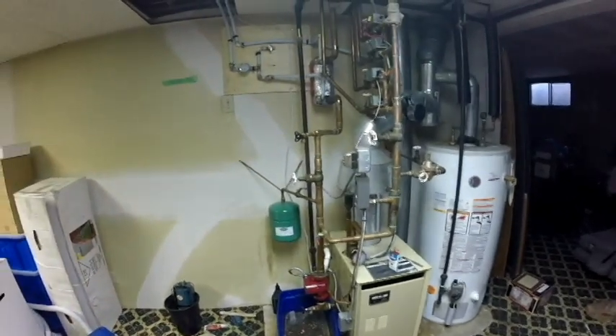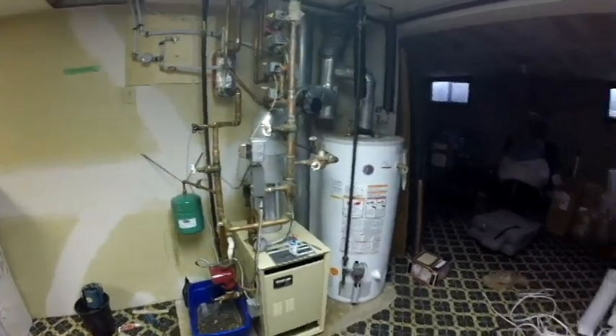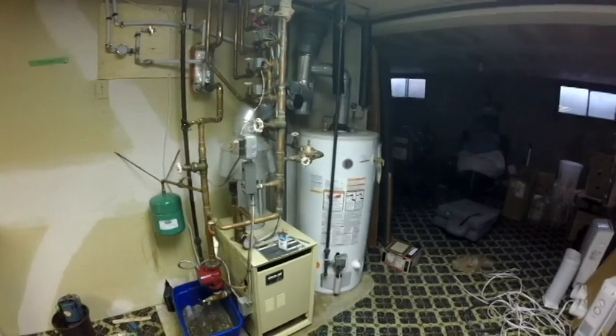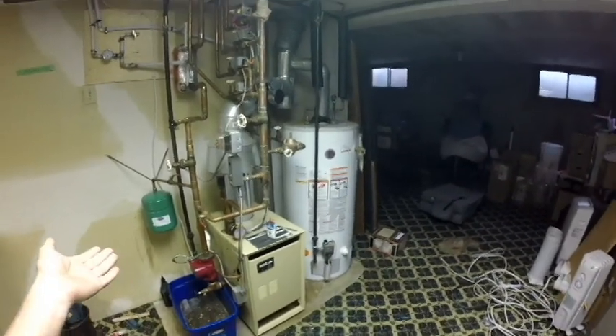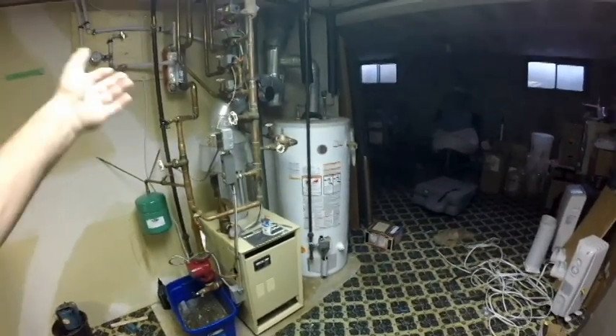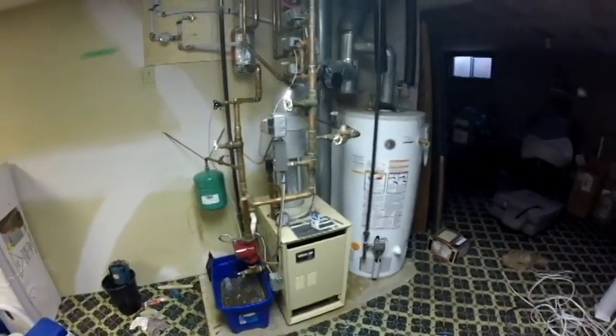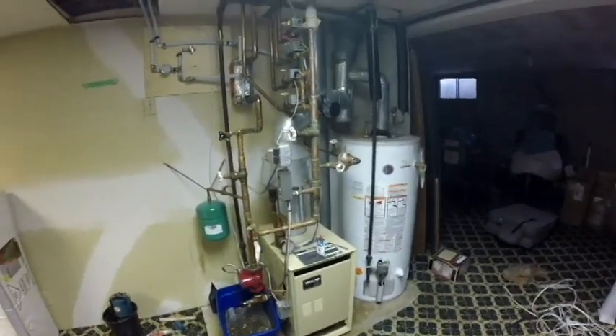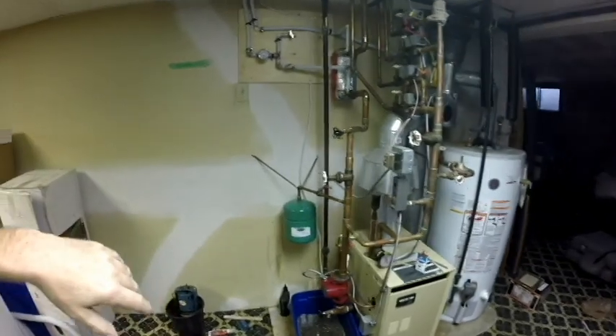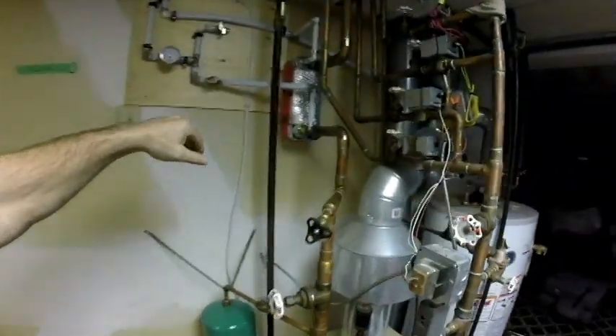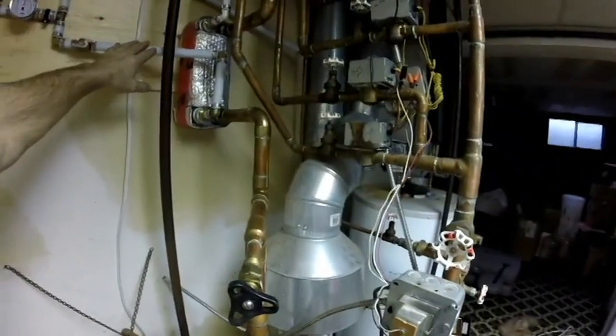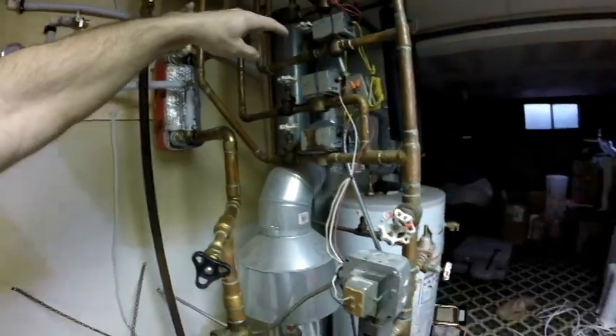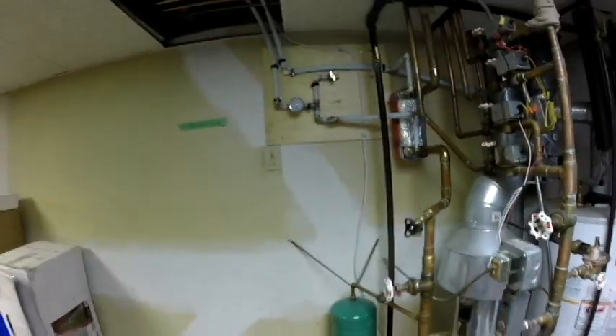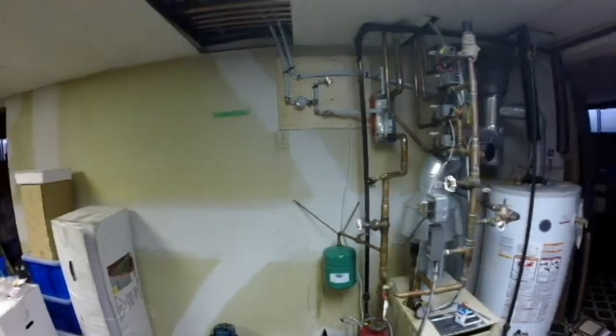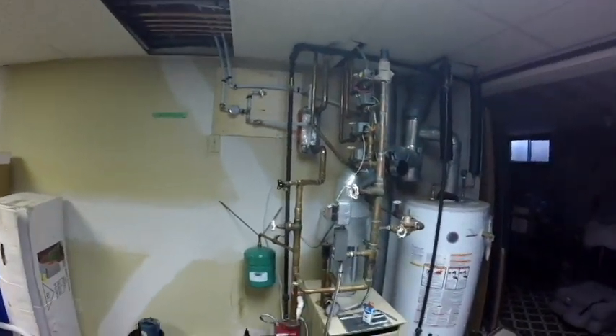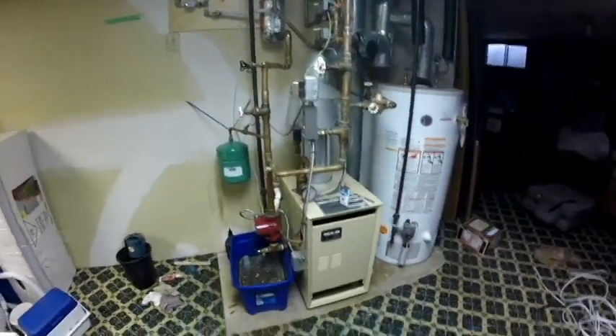In the summertime, this thing will be solar heated solely for the hot water usage, because you still need hot water year round for washing clothes, showering, whatever have you. But obviously the heating system will not run in the summer, so the zone controller will be bypassing the plate exchanger, but will constantly be pumping through to heat the hot water tank. So the system will run 365 days a year. So there you go. Let me know any comments that you have.